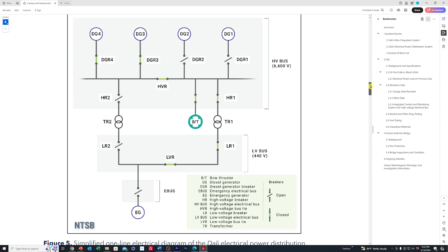Herein lies the rub, though. You see, even though these two generators were on and still giving power to the main engine, the problem is some of the systems driving the main engine require the lower voltage, like the pumps. So even though the main propulsion diesel engine was independent of the vessel's four diesel-driven electrical generators, the loss of power to the pumps required for its operation resulted in the main engine being automatically shut down, and the vessel lost main propulsion, meaning its propeller stopped.